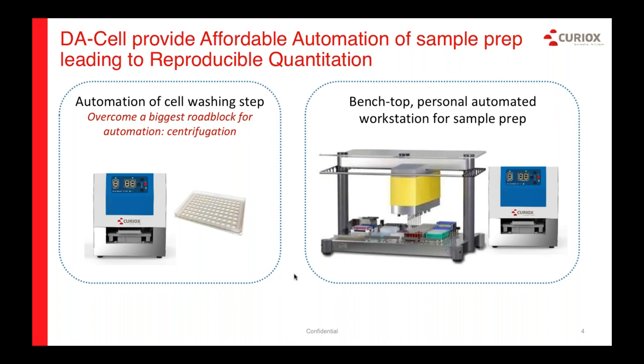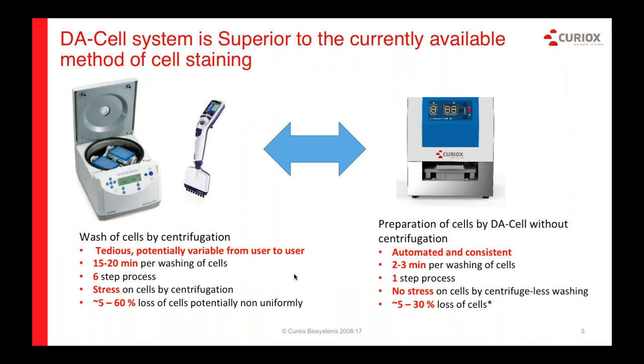We've introduced the DA cell washer — DA for DropArray — to wash cells in a 96-well format and remove user variation that occurs during centrifugation, aspiration, or flicking. We are working on the next generation, which will be a fully automated workstation including addition of reagents to cells, incubation, and essentially surface staining and/or intracellular staining protocols from start to finish. In a conventional wash process, scientists use a centrifuge and a multi-channel pipette; two centrifugations take 15 to 20 minutes. In contrast, DA cell completes the entire wash automatically in two minutes without centrifuging the cells, so cells do not experience any external forces or stress.